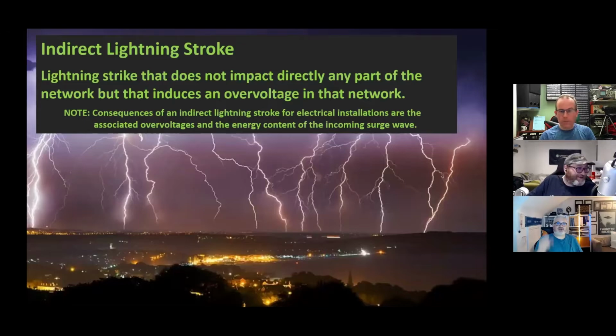Indirect lightning stroke - this is one of the errors and omissions as far as I'm concerned from the 18th edition. We talked about stroke, but it wasn't in the regs. Indirect lightning stroke is a lightning strike that does not impact directly any part of the network, but induces an overvoltage in that network - for example, striking the ground where there are cables beneath. The note says consequences of an indirect lightning stroke for electrical installations are the associated overvoltage and the energy content of the surge wave.